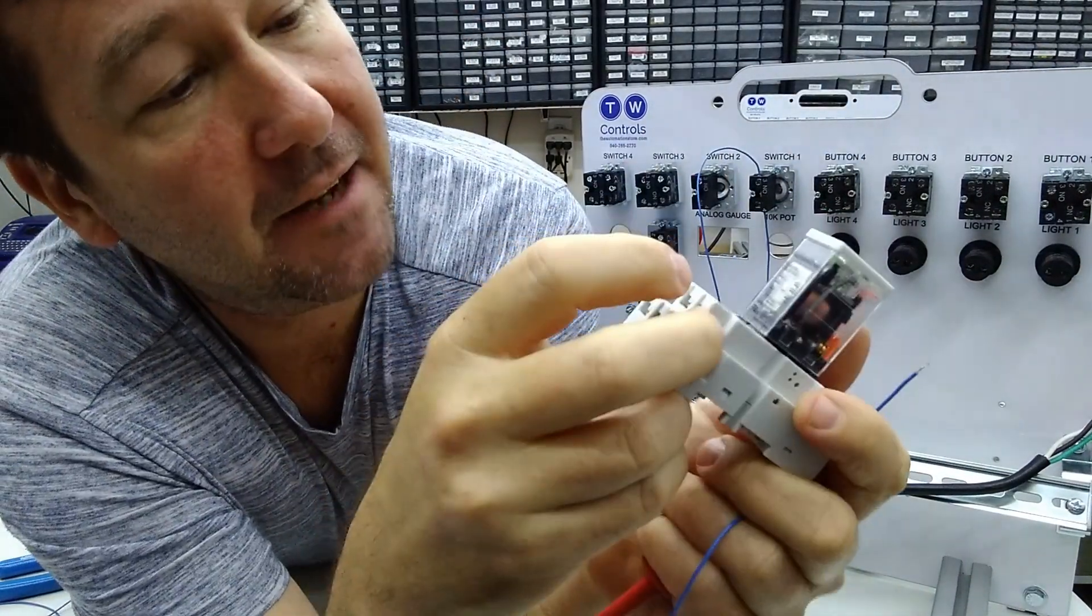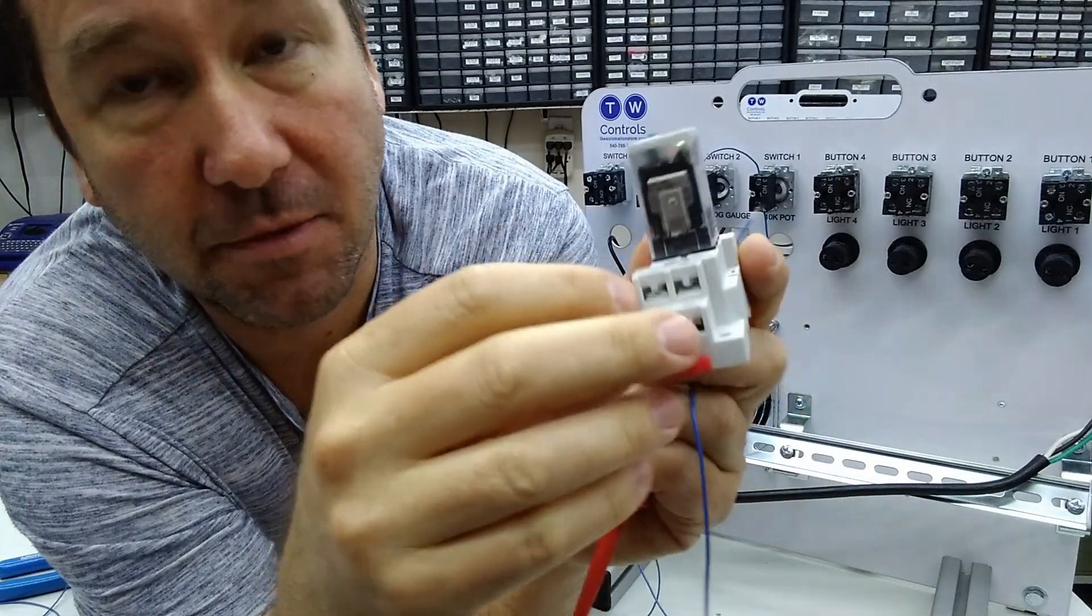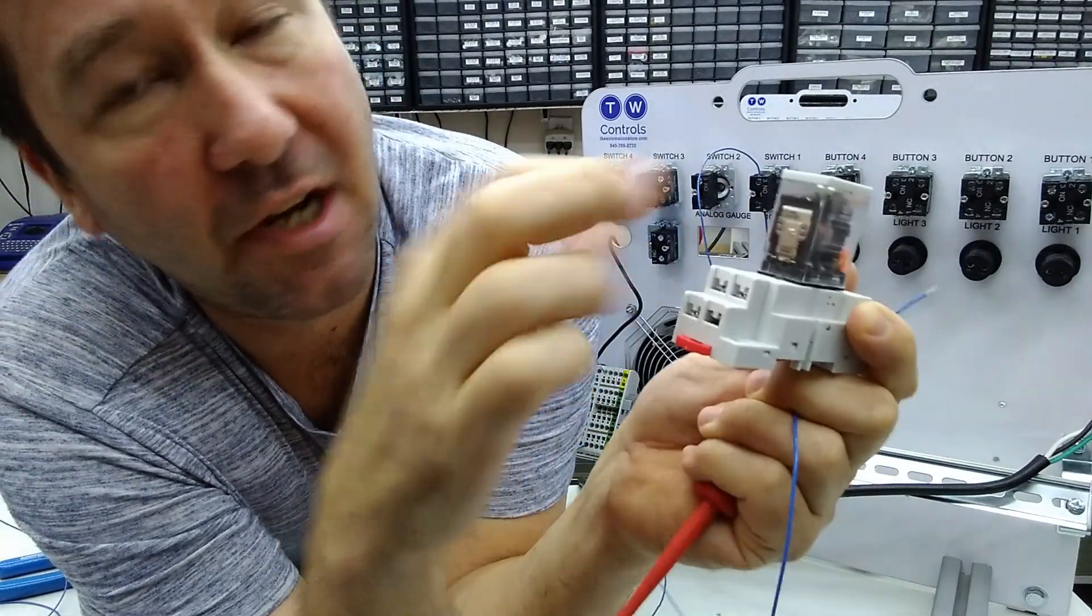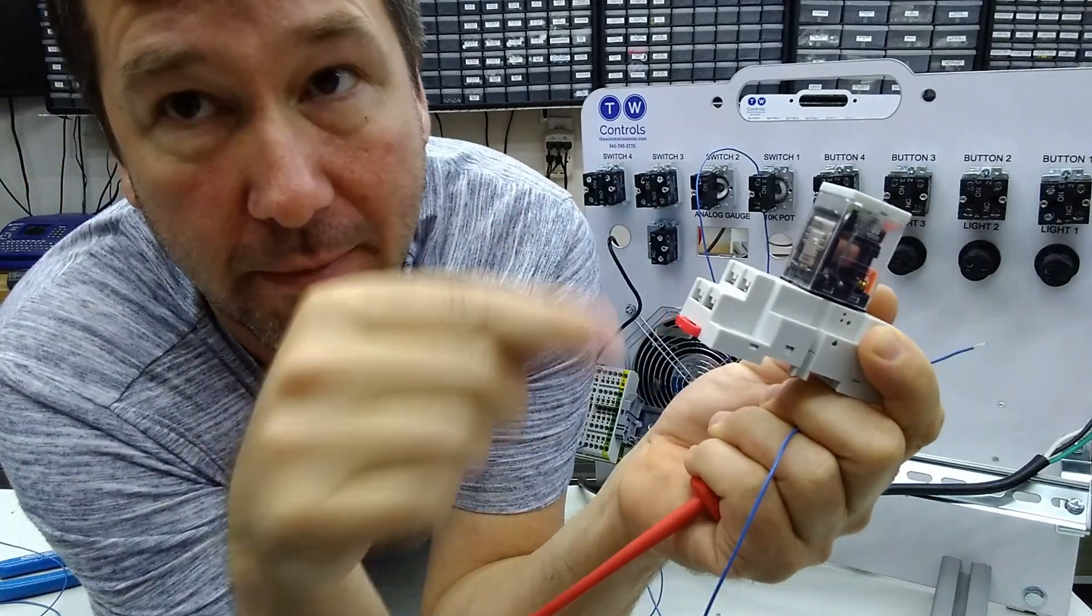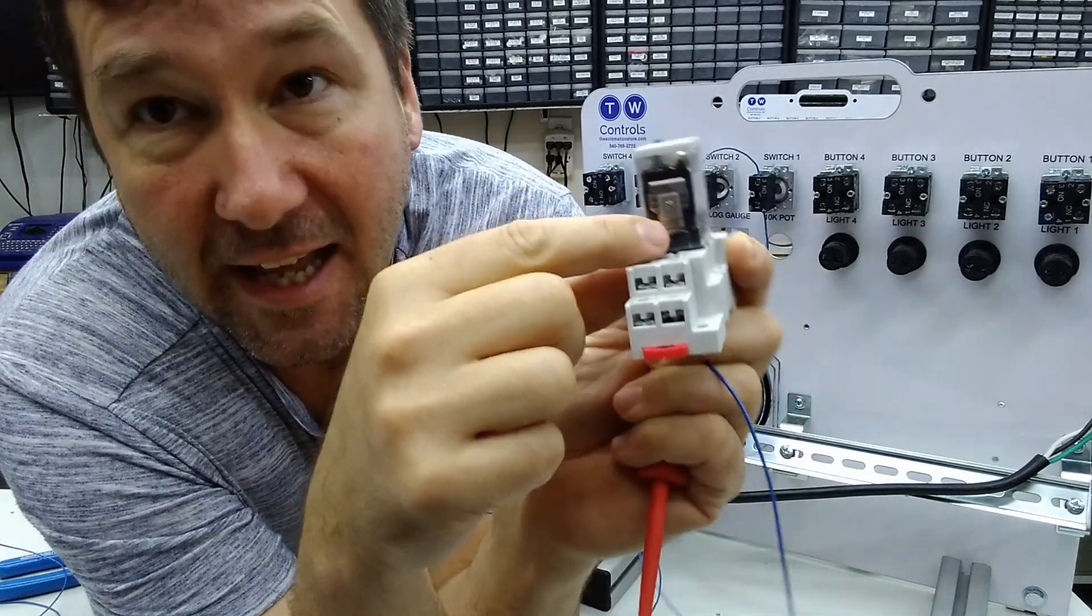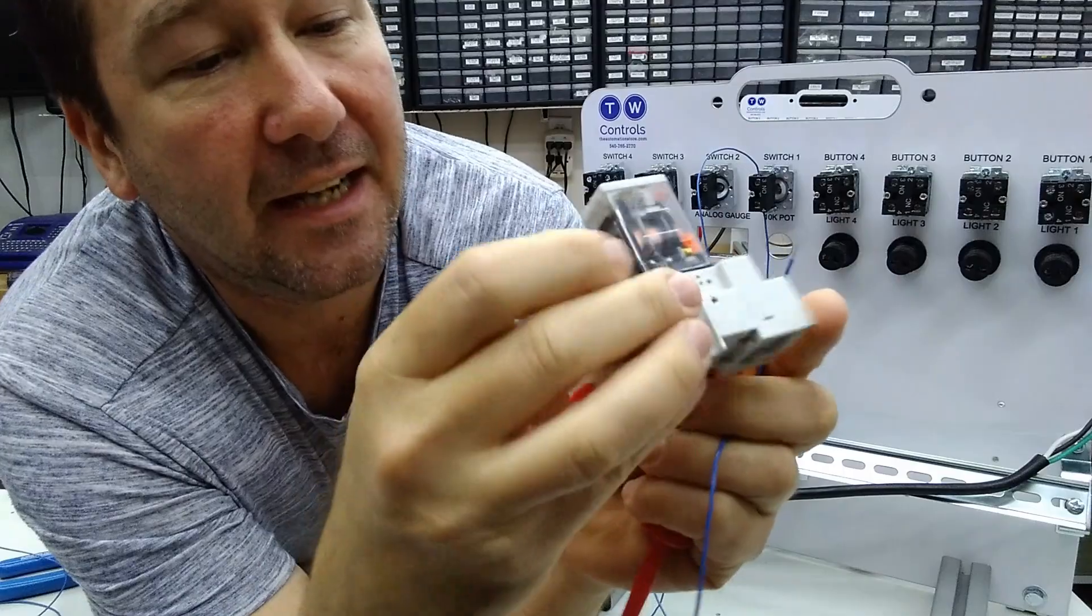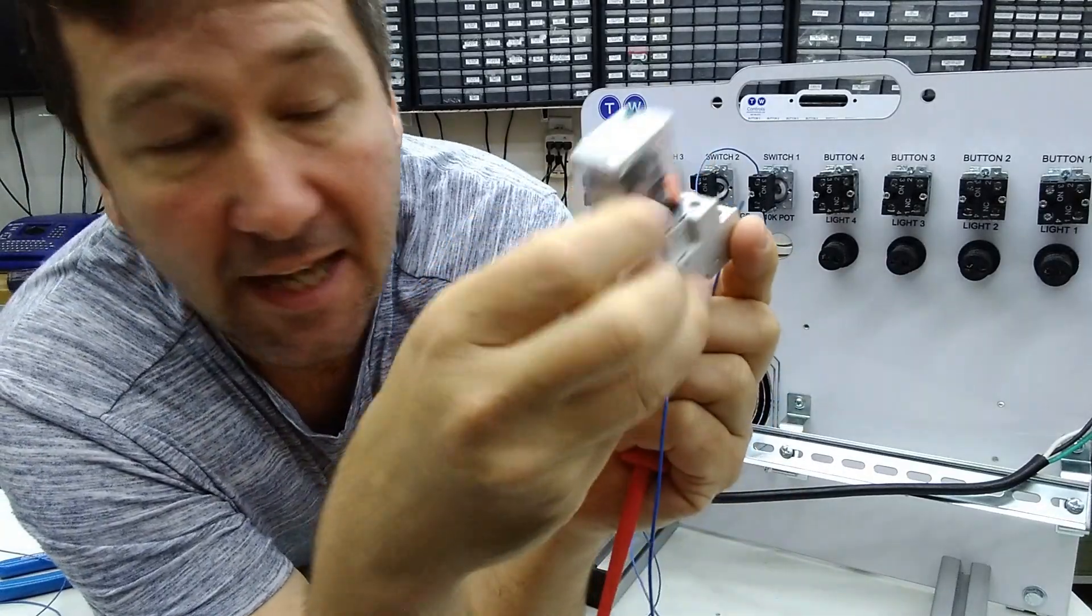You'll have to look at the diagram and figure out which one of these terminals is which, but usually you'll see a symbol for wire being curled up, and that is the coil. And in this case, it is A1 and A2.